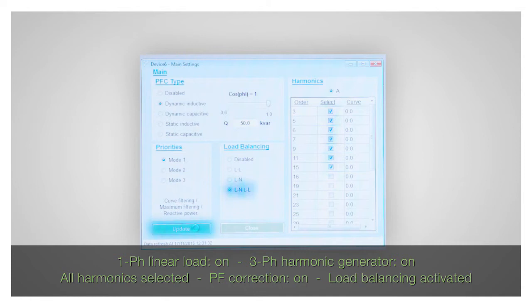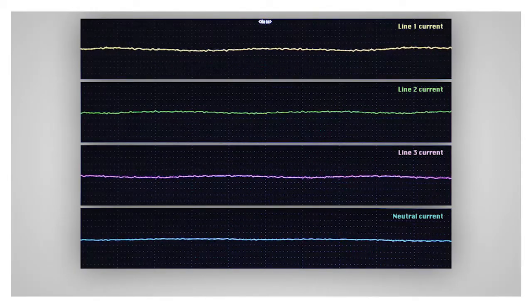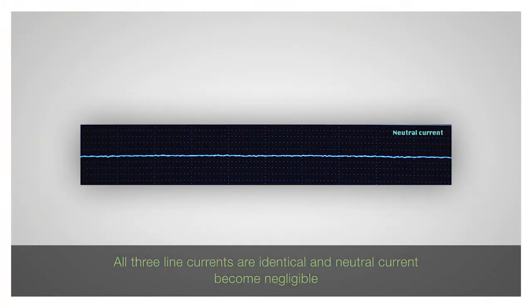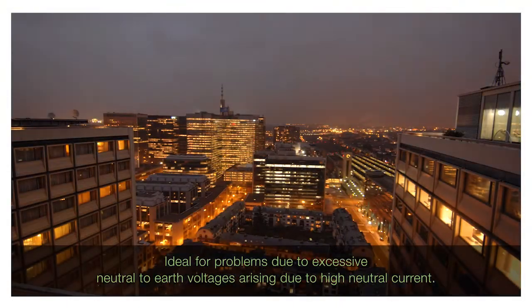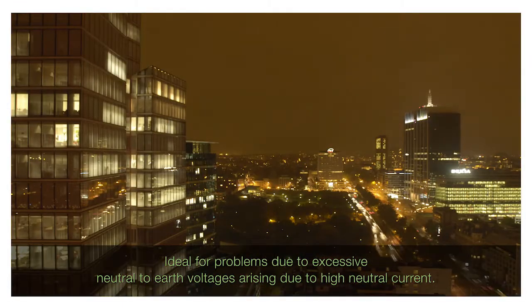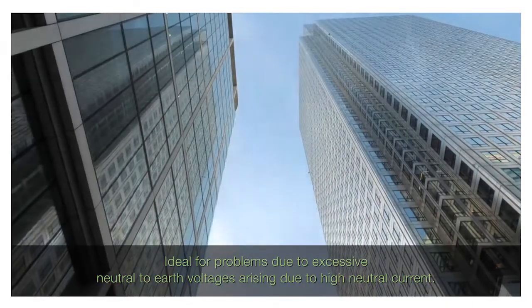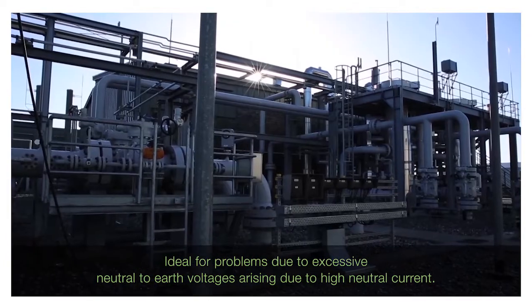As a next step, the filter's balancing features are selected as well. This results in the supply currents becoming virtually identical. At the same time, the neutral current is reduced to a negligible level. This feature of the PQF four-wire active filters makes them ideal for applications where neutral conductors have to be offloaded and where problems due to excessive neutral-to-earth voltages have to be addressed. In a similar fashion, the power factor (cos phi) of any installation can be corrected.